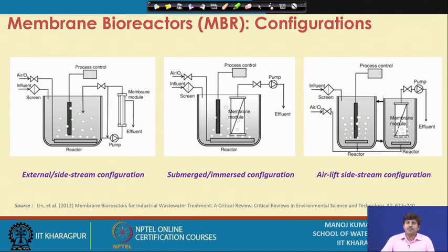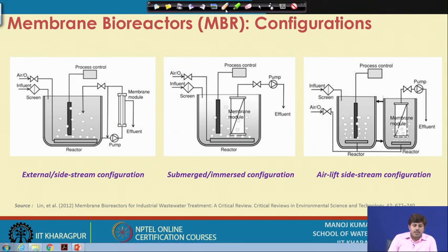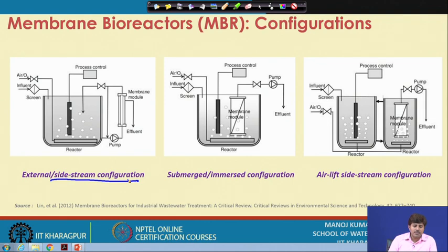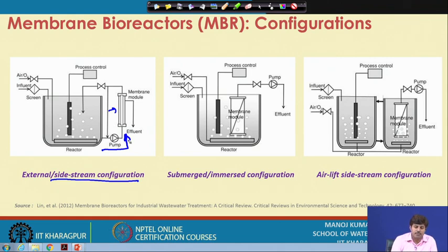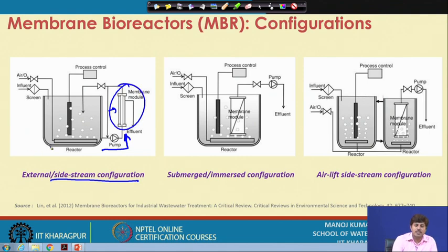There are two popular configurations of the membrane bioreactor. The first is the external or side stream configuration, which is the oldest configuration. In this setup, the membrane process is not within the reactor but outside it — a side stream from the aeration basin is passed through this external membrane, and the retentate is pushed back to the reactor.